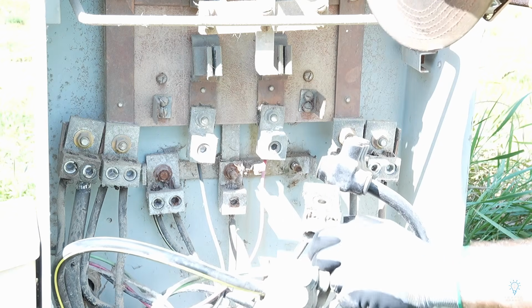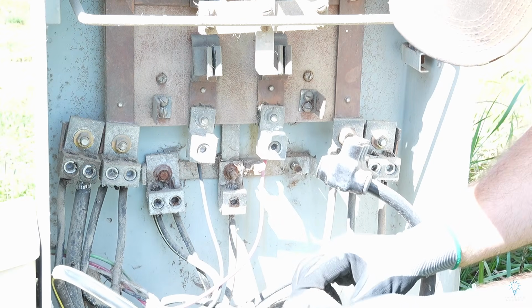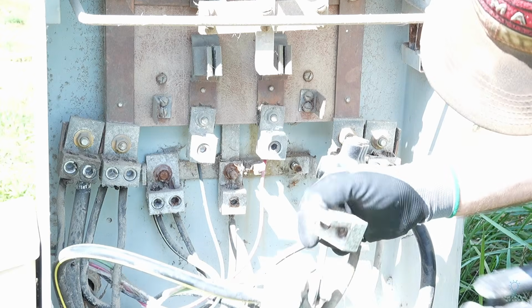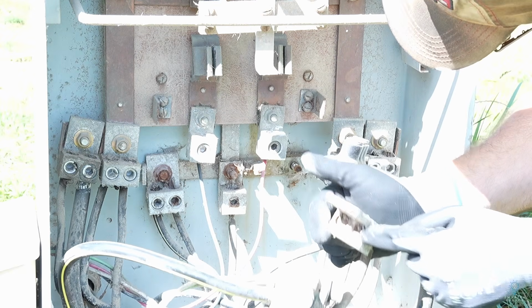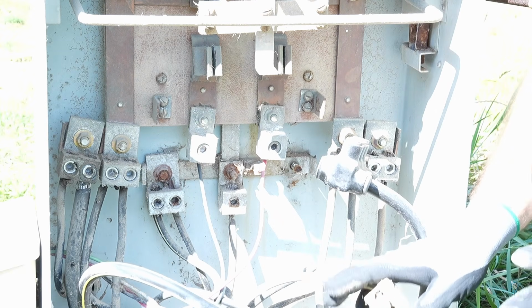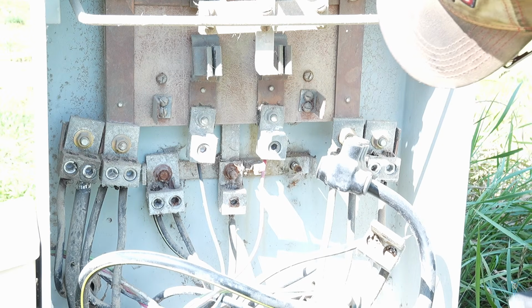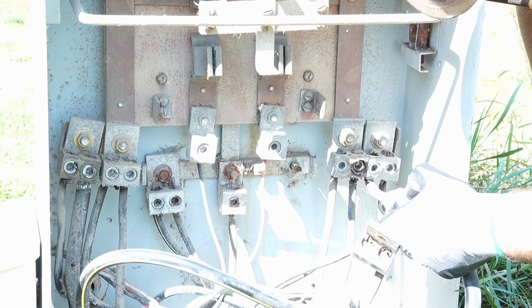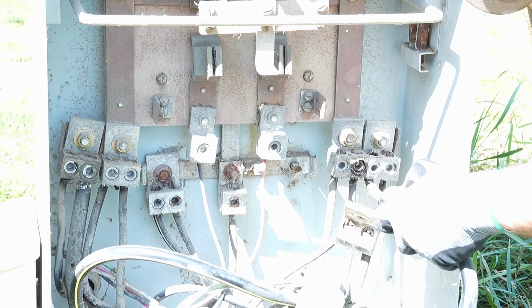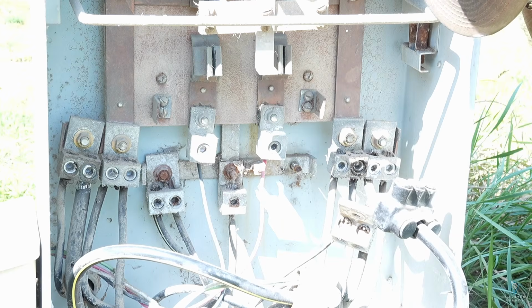Oh, that bus bar doesn't look bad at all. Yeah, the back of the lug still looks okay too. I'm guessing the corrosion issue is in the actual connection here. That makes me feel a lot better about this. A lot better. I see we've got a loose hot here going to the house. That's fantastic. We'll get that tightened down also.